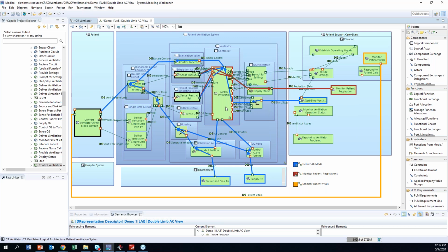And so you would want to basically simulate, or create a model that could show how the ventilator and its compressor, the inhalation air generator down here, produces air and sends it to the patient. That's where you might have to have a model of the patient to see what the behavior is.